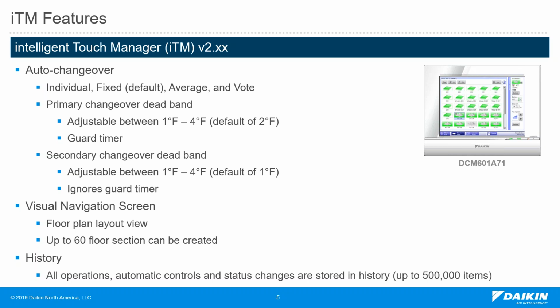From the display and visual navigation side, the user can use the ITM icons layout view, or the floor plan layout view. So there are two different views we can use on the ITM, and we use the floor plan layout view as another tool when we have the BACnet client, and we use graphics for other equipment using that feature. Up to 60 floor plans can be created inside the ITM. And for history, ITM can record up to 500,000 items.